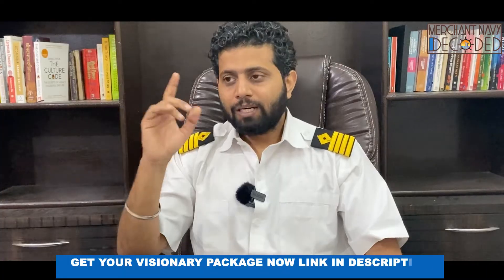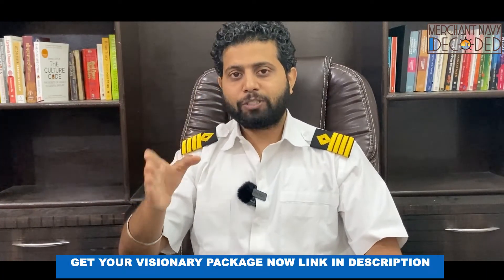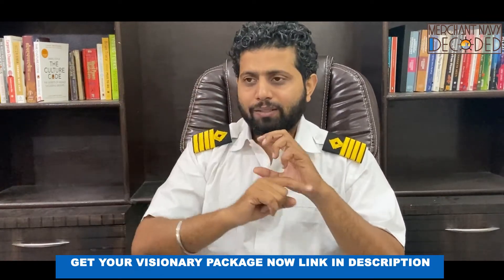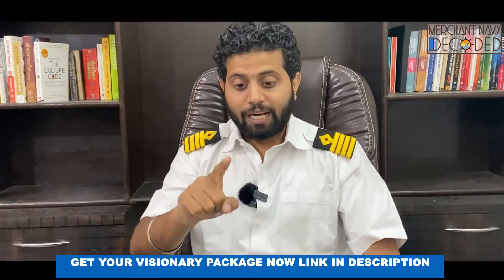Let's go for a pump characteristic curve round. Pump characteristic curve plays a very very important role on board ship. I have talked to 4th engineers, 3rd engineers — you guys read or mug up the characteristic curve but you do not understand its practical implication. In this video I have discussed that in detail with live practical examples. For a centrifugal pump, if the motor current has increased, it can not only be that the bearing has got damaged — one of the most important reasons can be that the flow has increased. For a positive displacement pump, if the motor current has increased, the reason can be the discharge pressure in the line. In a centrifugal pump it's the flow that matters, and in a positive displacement pump it's the discharge line pressure that matters.